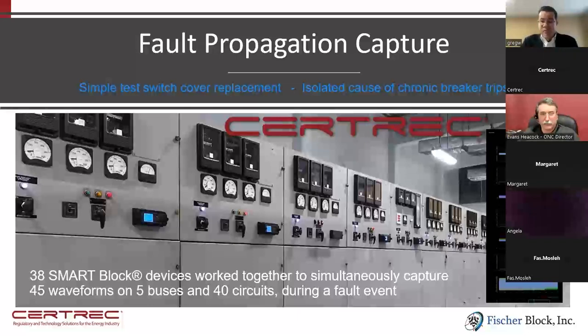And therefore, the sequence of events is well beyond what a typical SOE capture is. So not only do we get the breaker trip and the signal to the breaker, but we also capture the fault signature and how it propagates across the buses, the adjacent buses, and all respective feeders. So it's a much more encompassing SOE picture, and it helps primarily with nuisance trips, whereby there are many circuits on the grid that have a propensity to trip breakers, and they can become very difficult to understand why that breaker's tripping. Many times the relay engineer doesn't even have a waveform to look at. And when they do, sometimes that can be difficult to determine the cause. However, if you're able to see an SOE sequence of events analysis across many buses and feeders in a given plant, then you can know where it started and how it propagated. And so that's one implementation and use case for our technology.